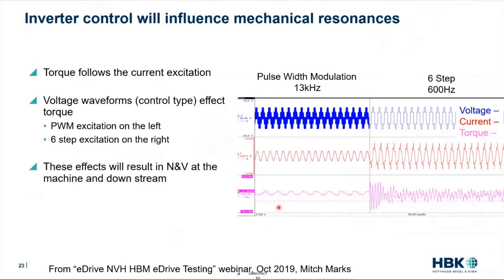There are a variety of control techniques. The one we just showed is PWM excitation — pulse width modulation. We've established that inverter control will affect mechanical resonances. There are different control techniques, meaning different ways we can turn that inverter on and off, with different effects. Keep in mind that torque follows the current excitation. On the left-hand side of my picture, I have a pulse width modulated signal shown as thick blue triangles, where blue represents voltage.